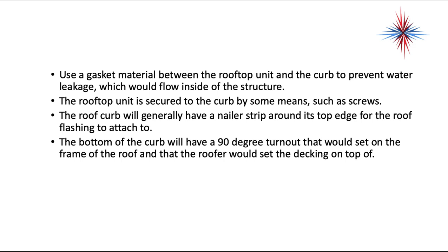We use a gasket material between the rooftop unit and the curb to prevent water leakage, and it also provides a little bit of vibration resistance as well. The rooftop unit is secured to the curb by some means, such as screws or bolts. The curb will generally have a nailer strip around its top edge for the roof flashing to attach to. The bottom of the curb will have a 90-degree turnout, so it would set on top of the frame of the roof, and the roofer can set the decking on top of it.